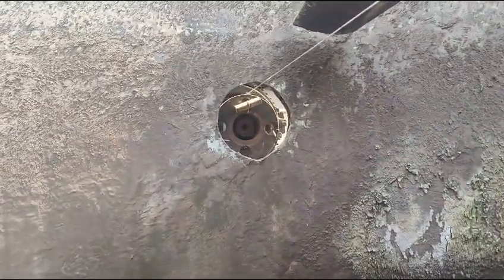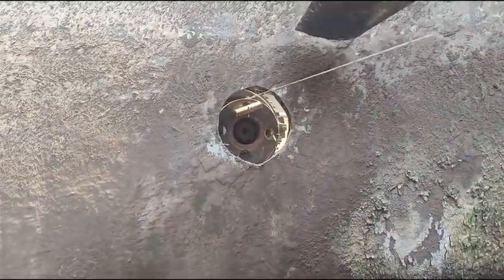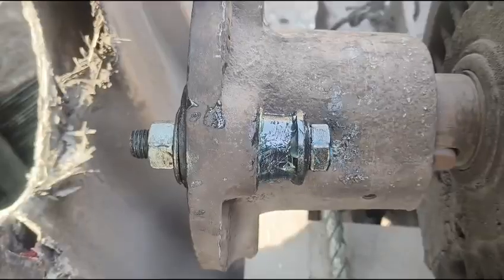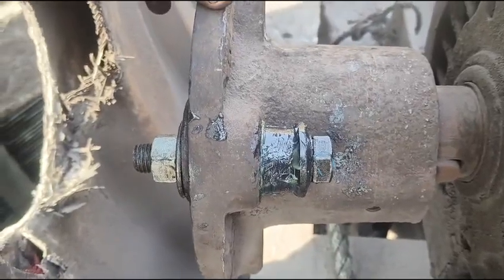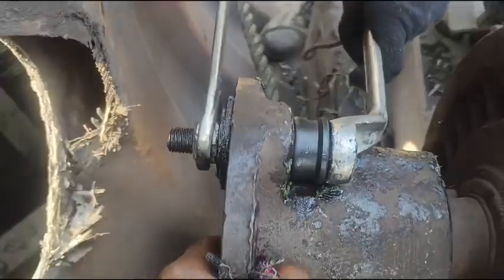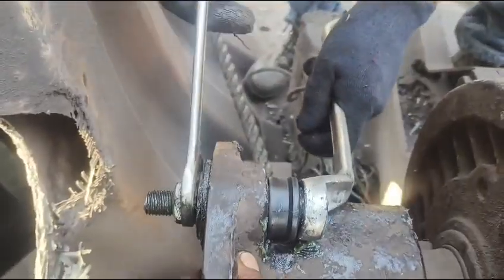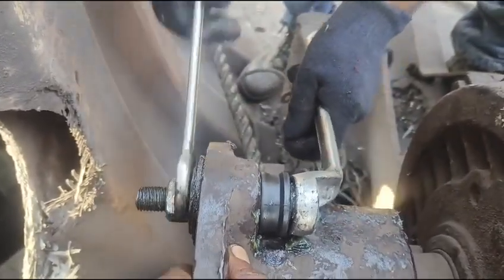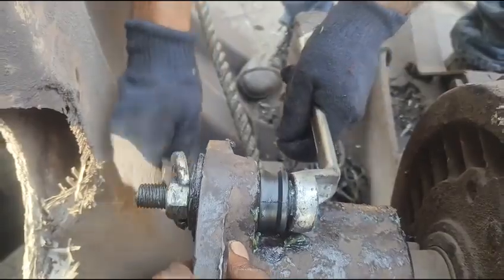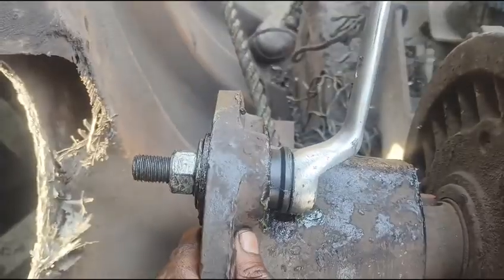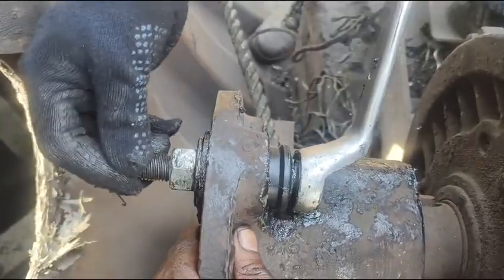Adjust the motor position horizontally and vertically until the gap is removed. This method checks for parallel misalignment. Insert the motor coupling bushes safely. Insert all four bushes in the coupling.